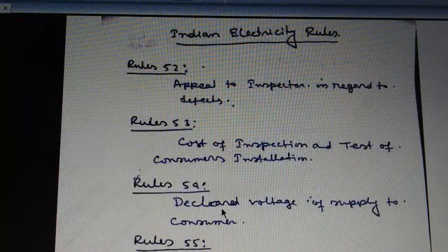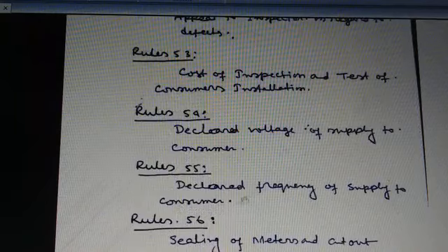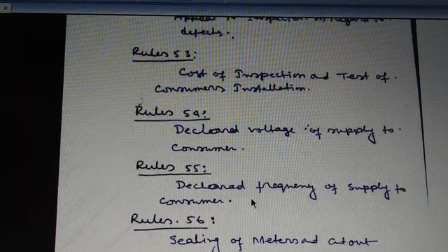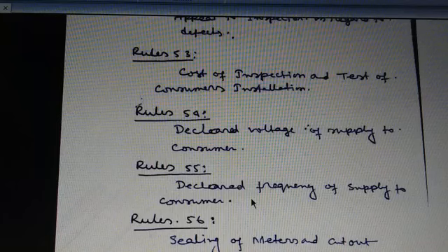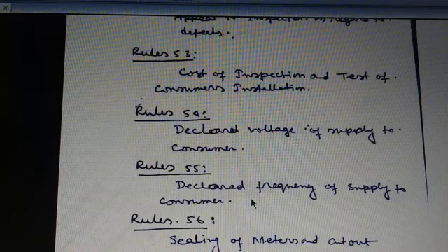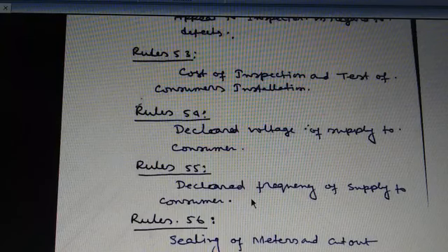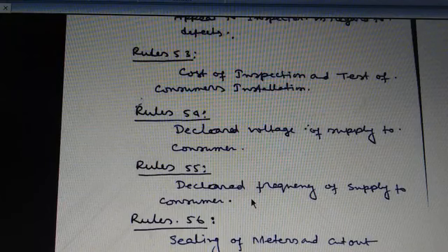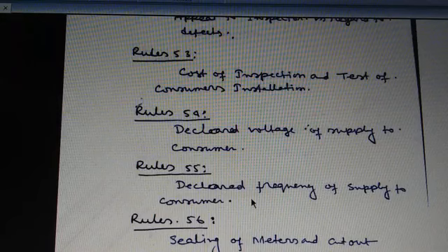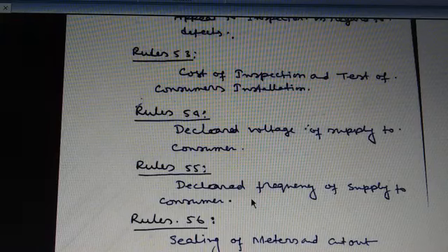Next point, rule number 55. Declared frequency of the supply to the consumer. Except with the written consent of the consumer or the previous approval of the state government, a supplier shall not permit the frequency of the alternating current supply to vary from the declared frequency by more than 3%. That means we know our supply frequency in our country is 50 Hz. So in our country a 3% tolerance in frequency is allowed. That means 3% of 50 Hz is the tolerable range.